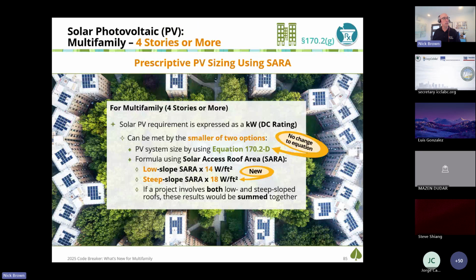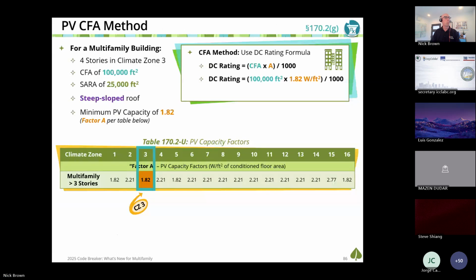For high-rise multifamily, same SARA multipliers instituted in the code, same approach. The lower of the two calculations is what governs. So here's an example, low-rise multifamily. Actually, sorry, this is high-rise multifamily, 4 stories, 100,000 square feet. We find factor A in our chart, 1.82, and we get 182 kilowatts via the CFA method.